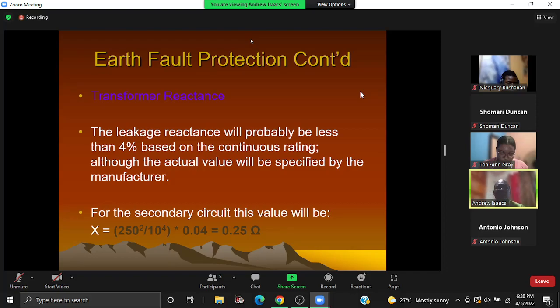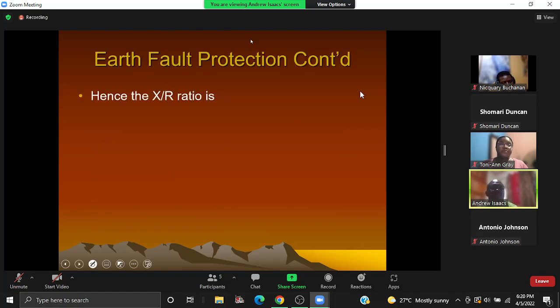For the reactance of a transformer, they're about 4%. Of course, you'll get that from the manufacturer. And that would equate to 0.25 ohms. And so the X to R ratio of your transformer would be 0.25 over 0.9. Note I use 0.9 because that is the resistance, the equivalent resistance.